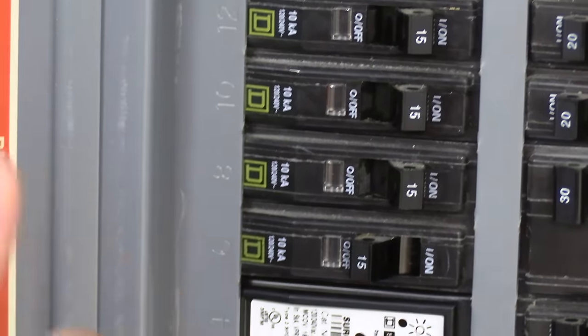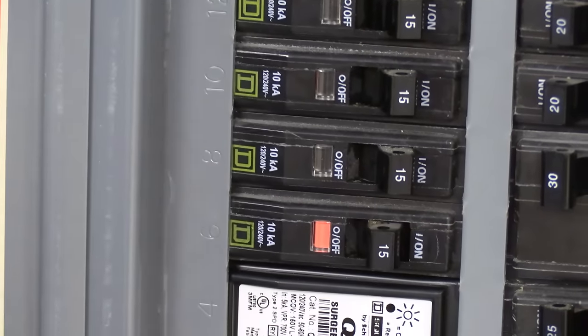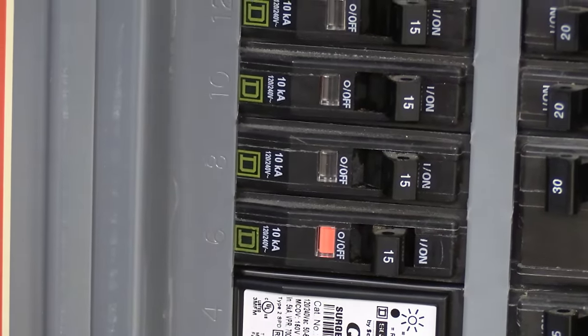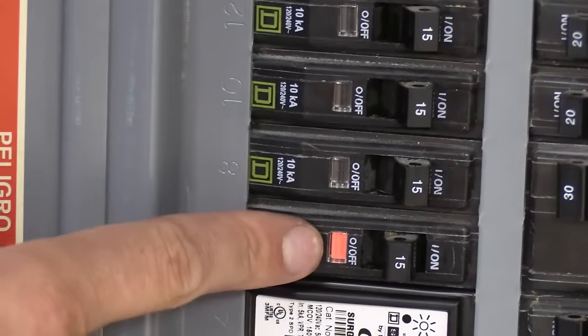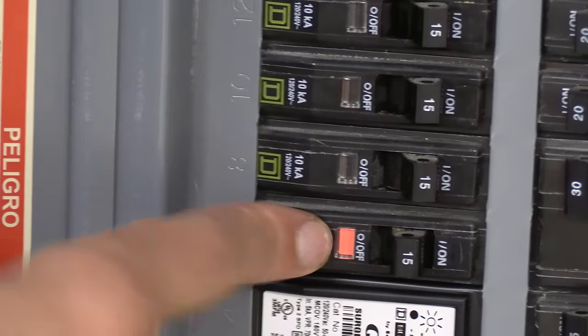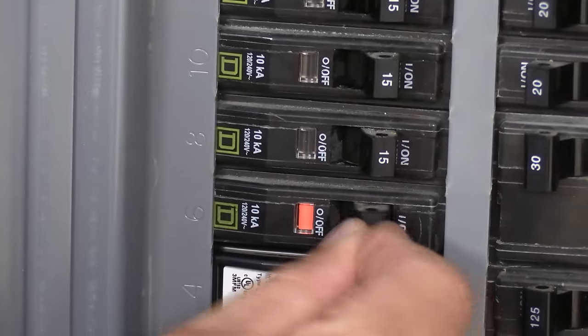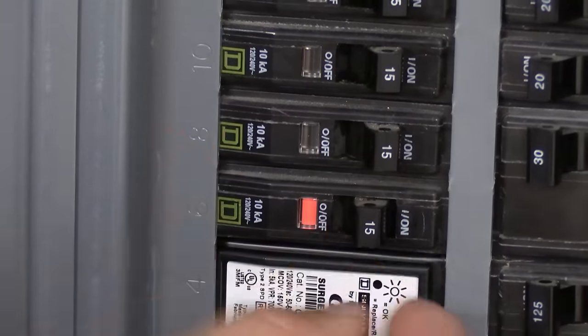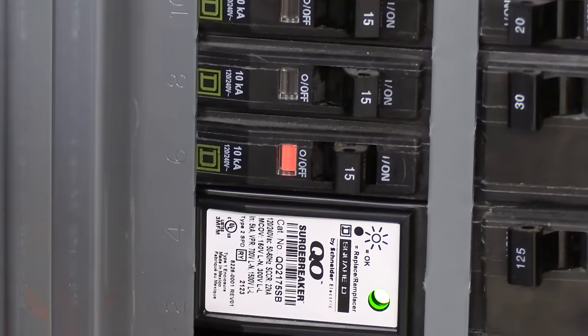Now let me show you what the trip position looks like. See, that's a shorted breaker. And now we've got a red flag and it's in that middle position. And it's wobbly. See, there's some resistance. That's fixed in that position, but that's tripped.